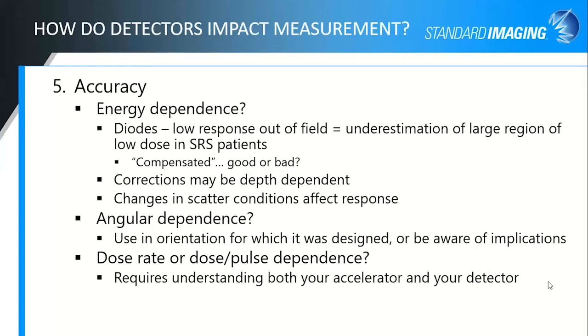So dose rate and dose per pulse dependence also are not quite as critical with scanning as they are with output measurements, because you're usually measuring in a consistent fashion. With relative scanning measurements, usually the dose rate or the dose per pulse is being maintained. I'd add a caveat that as you go to your smaller fields, that can affect dose rate or dose per pulse. And therefore, if you have a detector that is more highly sensitive to those changes, or you're at borderline saturation or something like that, then that can affect your scanning measurements as well.